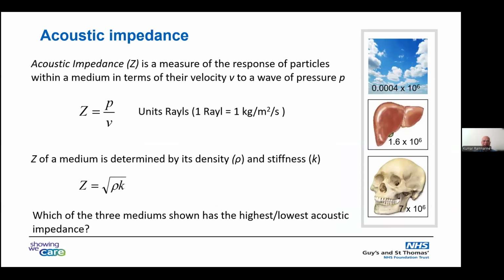Acoustic impedance is another concept that's really key to ultrasound imaging. So acoustic impedance is defined as a response of the particles within the medium in terms of their velocity. So this is not the propagation wave velocity, not the 1540 meters per second wave velocity. This is the actual velocity of the particles as they're vibrating, oscillating due to the pressure wave. So that's the acoustic impedance definition. And that can also be defined in terms of the material density and stiffness as a square root of the density multiplied by the stiffness. The reason why the acoustic impedance is so important is because the acoustic impedance mismatch between materials, between interfaces, is what determines the amount of ultrasound that's reflected back. So the signal strength that's received by the ultrasound scanner will be dependent on the acoustic impedance mismatch between interfaces.